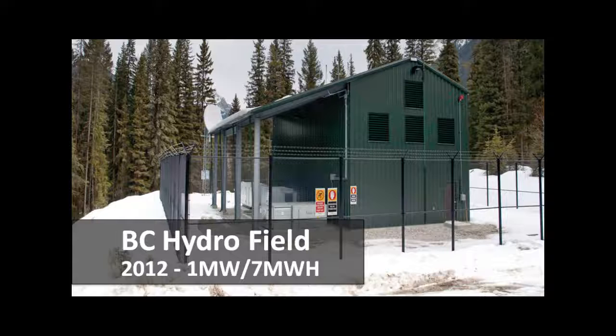Here we're looking at a microgrid created in Field, British Columbia, a town of about 300 people served by a radially fed 70-mile line. They had outages very frequently, sometimes lasting 6 to 24 hours. The outages were worsened because the line ran through a protected forest, so they couldn't trim trees to prevent them, and because the line also ran along a railroad, requiring coordination with the railroad and extending outage times. So back in 2012, a 1 megawatt, 7 megawatt-hour system was installed with the utility to automatically island in the case of an outage.